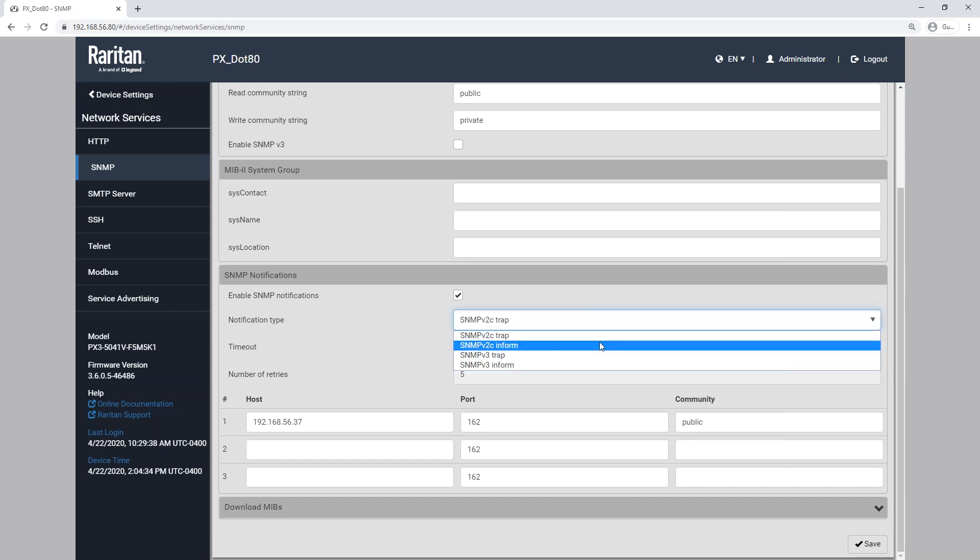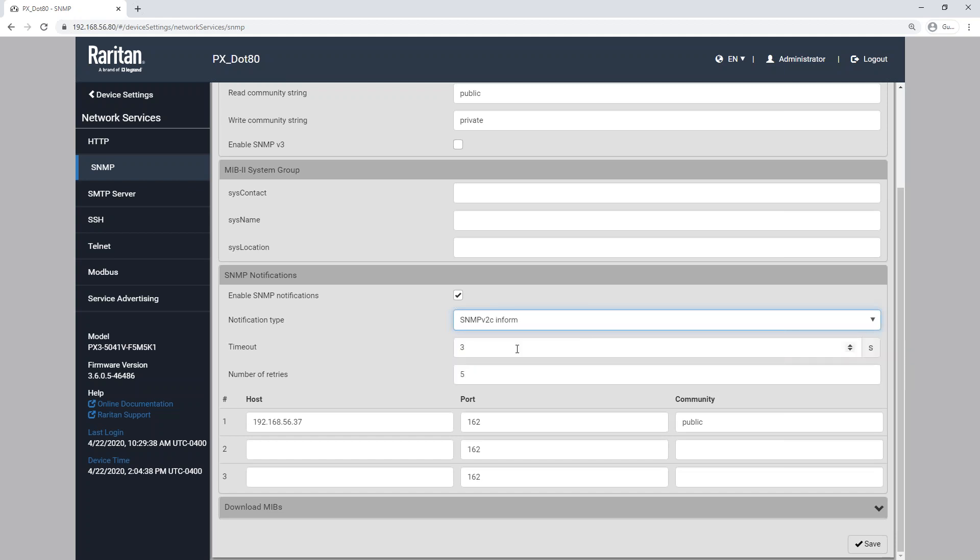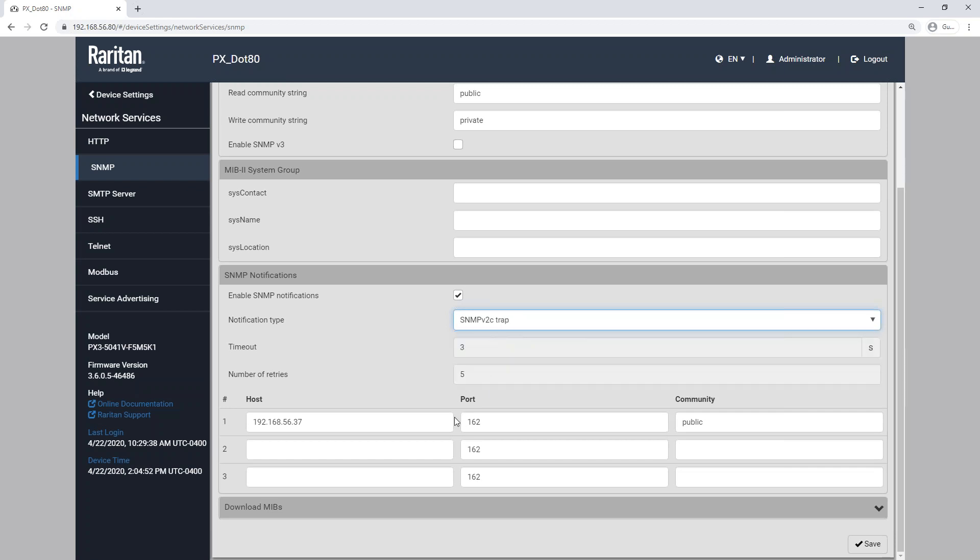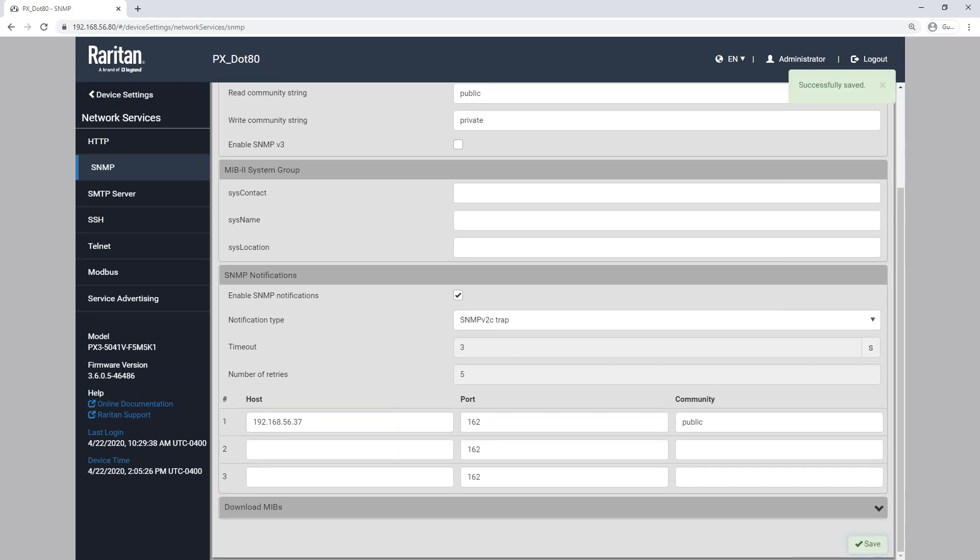So if your SNMP manager supports that, it's a good method to use. You'll see that when we select that, we have some options here. We have a timeout in seconds, and then we have the number of retries before the PDU gives up. For this video and training, we're just going to look at V2C traps. So down below, we have a host. So this is going to be the IP address or host name of your SNMP manager. Like I said, in our case, we're using Sunbirds PowerIQ. So I have our IP address plugged in here. The default port for SNMP traps is 162. This can be modified as needed, but we're going to leave it default. And then we have a community string. This is going to have to match what your SNMP manager requires. So with those fields filled out, we're just going to go ahead and click save.